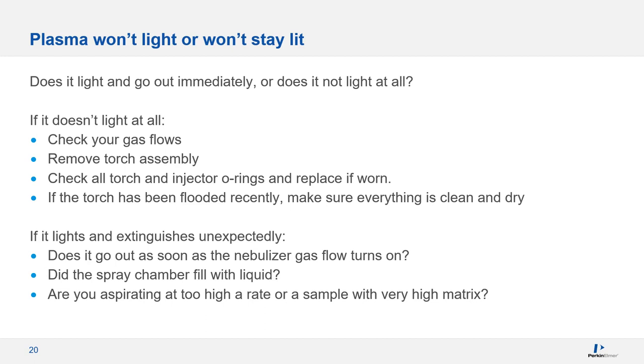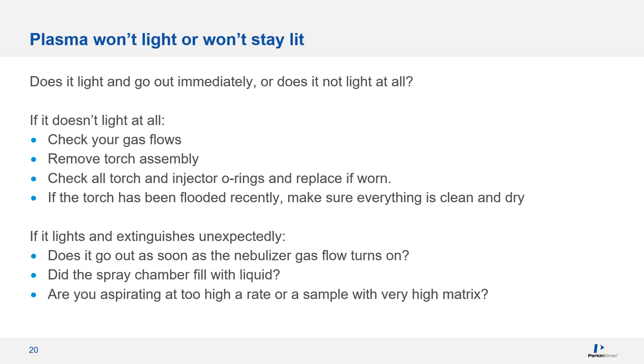If, however, the plasma lights but goes out quickly or unexpectedly, it's important to observe when precisely it goes out. It might be helpful to discuss the ignition sequence to understand this better. The first thing that happens when you press the Ignite button is the argon gases will all flow to purge out any air in the system. Next, the nebulizer flow will turn off. Then, the ignition will take place and there are a few seconds where the system allows the plasma to stabilize. After the stabilization time has passed, the nebulizer gas will turn back on and the peristaltic pump will turn on. If the plasma ignites and goes out right when the nebulizer gas flow turns back on, this indicates an air leak. When you're checking and tightening the connections in your system, be careful not to over-tighten.